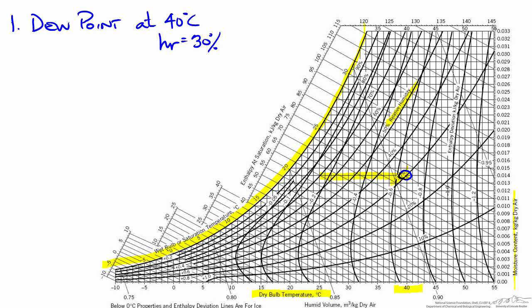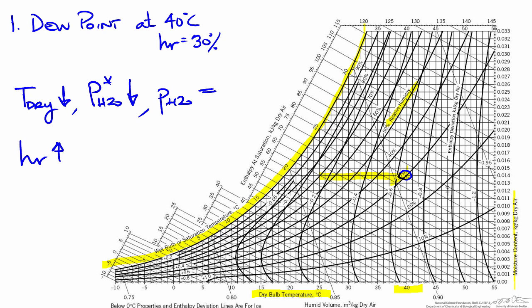So let's look at what is changing as we move to the dew point. If we are moving left, we are decreasing the dry bulb temperature. Since the vapor pressure is a function of temperature, the vapor pressure is also going to decrease. If we are not changing vertically — in other words, not changing the moisture content of the air — then the partial pressure of water is staying the same. So if we keep the partial pressure of water constant while decreasing the vapor pressure, the relative humidity must go up. And that is what we see as we move left: we start at 30% relative humidity, then 40%, then 50%, continuing to increase until we hit 100% at the dew point.